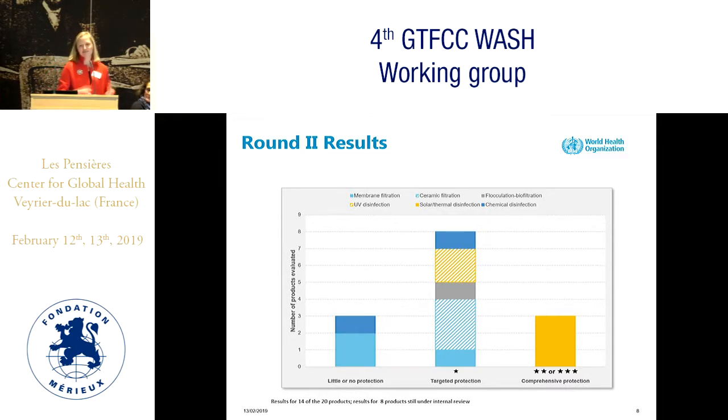So even in bore wells, you could have non-turbid water that had a high chlorine demand, and conversely, even in your surface water sources, you may have water that didn't have very much total organic carbon, and therefore the chlorine demand was lower. So the bottom line is that chlorination really requires a very site-specific approach.